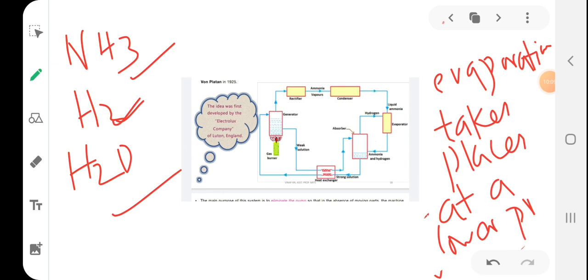Why is that happening? Because you know Dalton's principle, right? During the process of evaporation, the ammonia absorbs latent heat from the refrigerated space and thus produces the cooling effect. So what is Dalton's principle? The total pressure is the sum of the partial pressures of hydrogen and ammonia, right? So the presence of hydrogen will decrease the partial pressure of the ammonia. Ammonia will be present at a lower pressure, which means it will have a lower boiling point, at a lower temperature. So the process of evaporation gets enhanced, right?